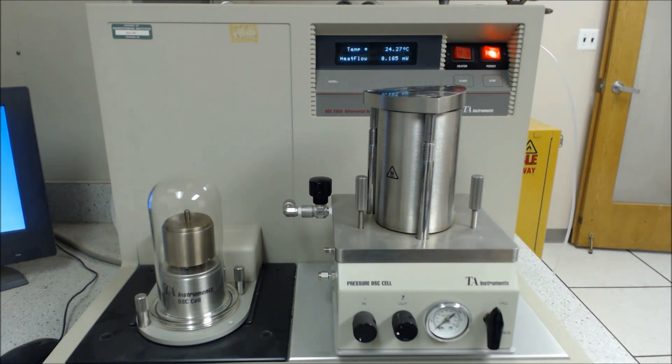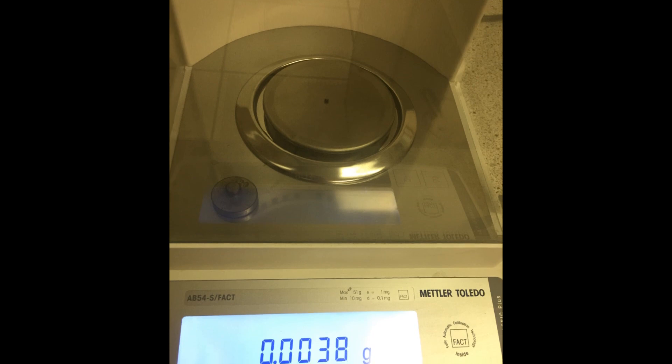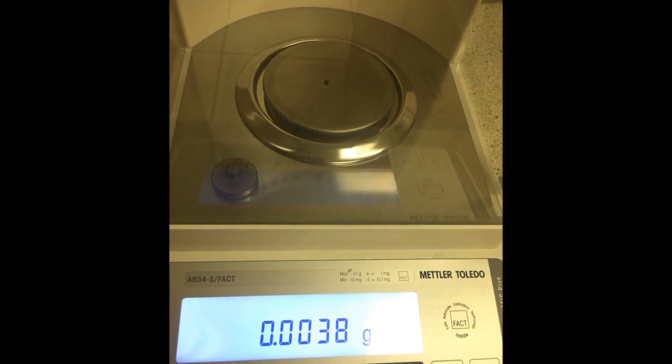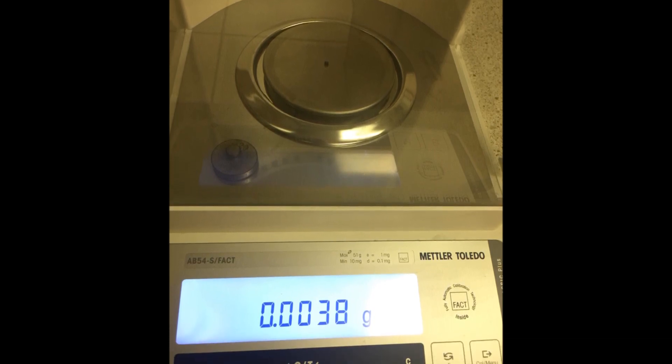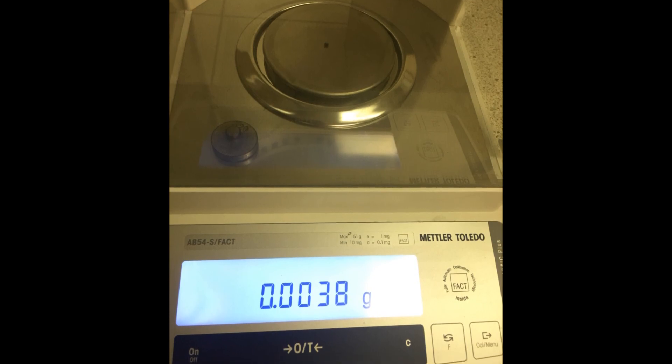Today however we will be focusing on the standard OIT cell for running these tests. To set up the test, first cut a 3.5 ± 0.5 milligram square specimen out with a razor blade. Place the specimen into a sample pan.